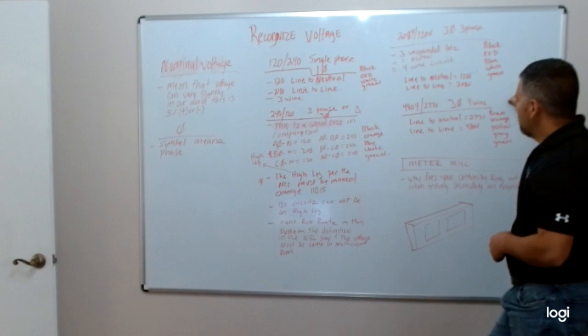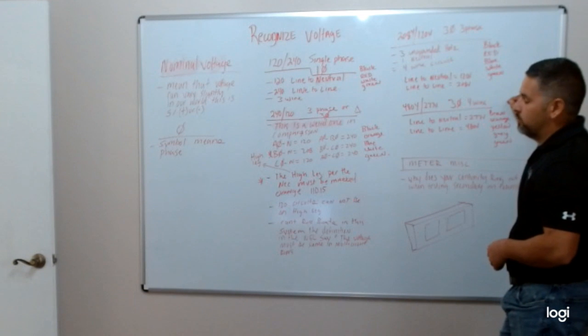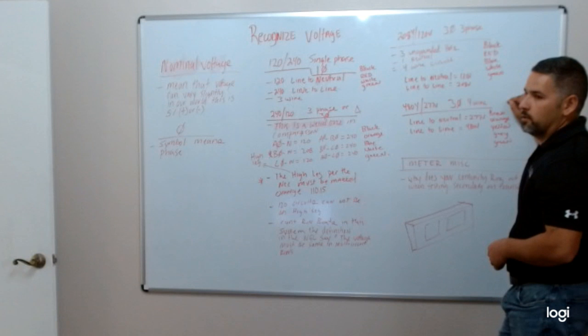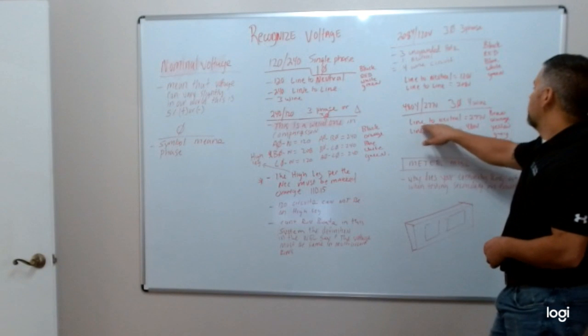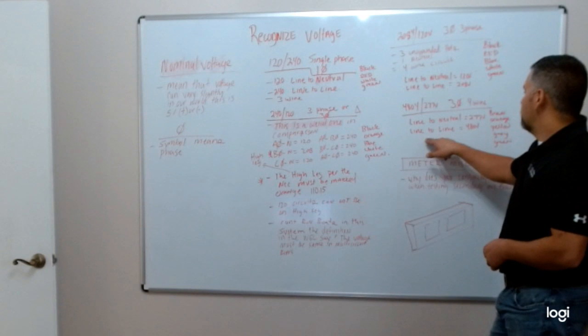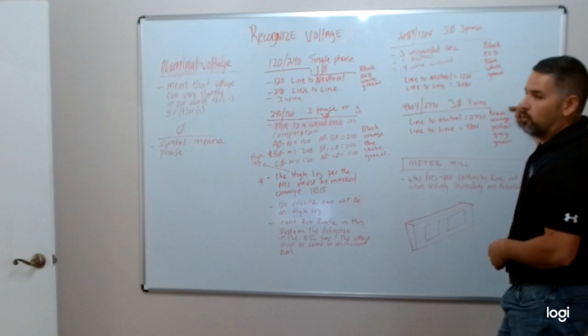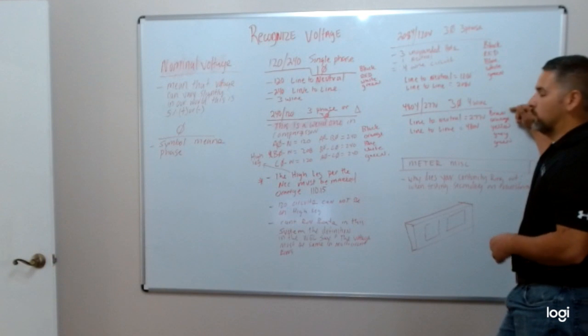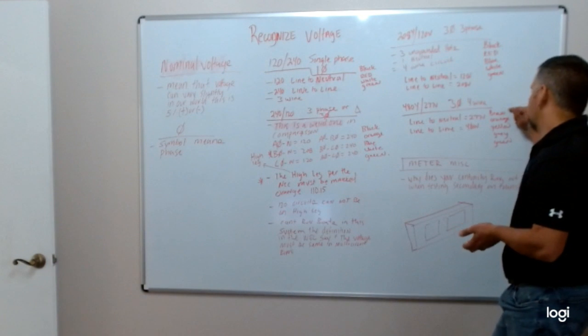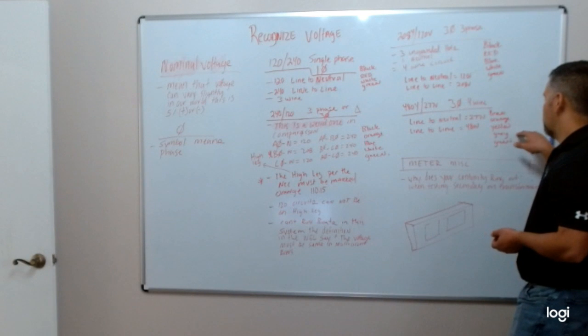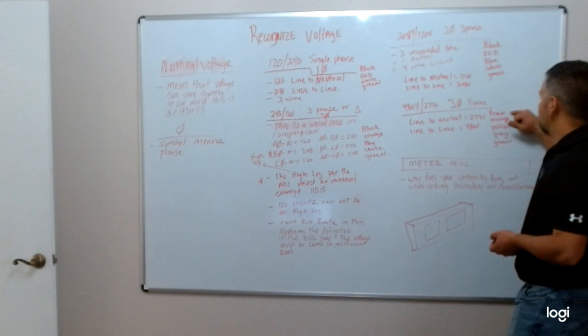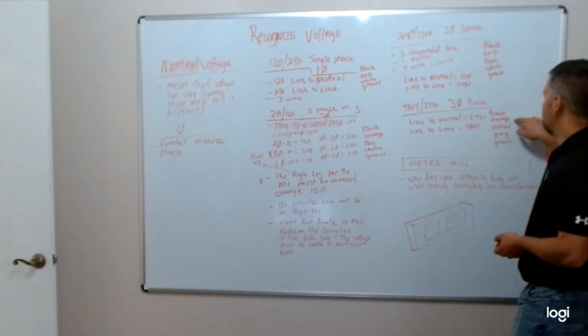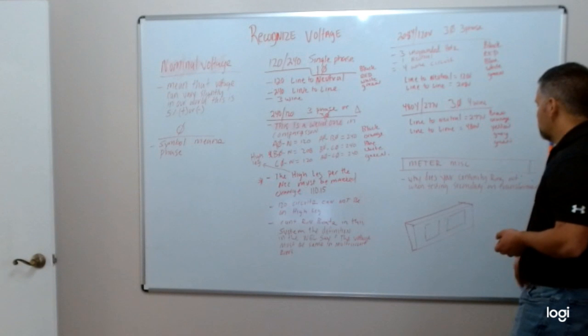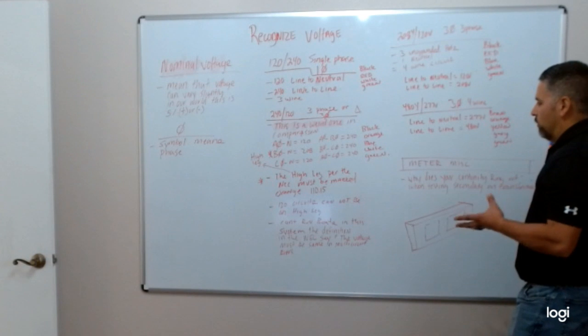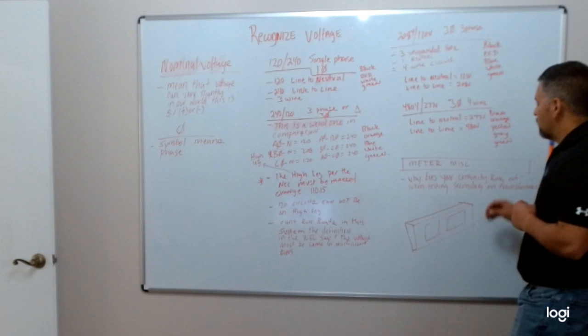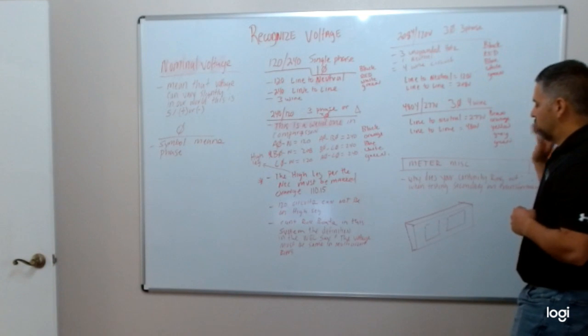Then we move down to 480, which is just going to be your normal lighting panel, motors, HVAC systems, stuff like that. Line to neutral, 277. Line to line, 480. The normal color coding that we use for this, and once again, it doesn't specifically say that these have to be the same, but gray and green do have to be the same. So brown, orange, yellow for A phase, B phase, C phase is going to be our color combination for the way we run things, and that is the 480/277.